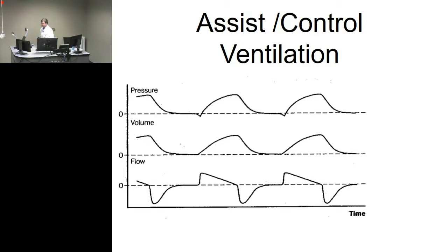That can be an indication that the exhaled tidal volume isn't completely there because the ventilator isn't sensing the full return. It gets down to the end and it's cycling off. It has to reset back to a 0 point, and it's just going to forget about the rest of that exhaled volume. And so that could be, maybe you have a cuff leak, maybe you have some problems with your ventilator circuit, or you could potentially have some problems inside of the patient itself.